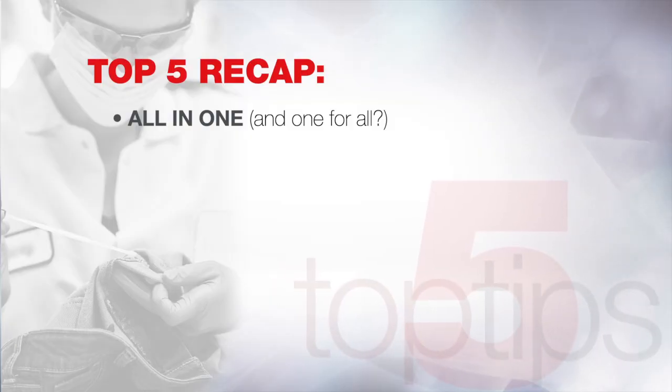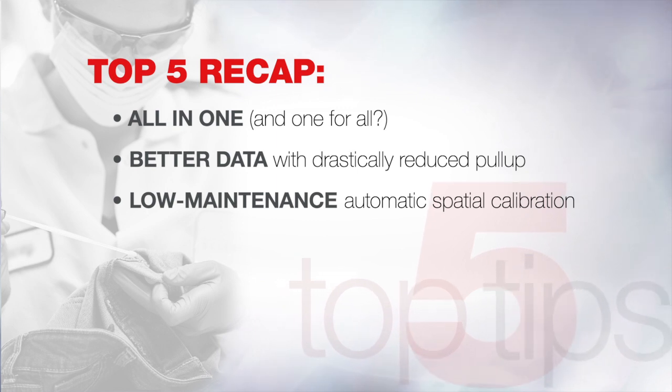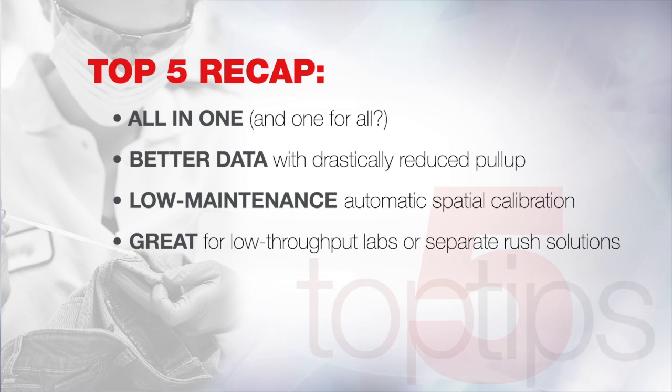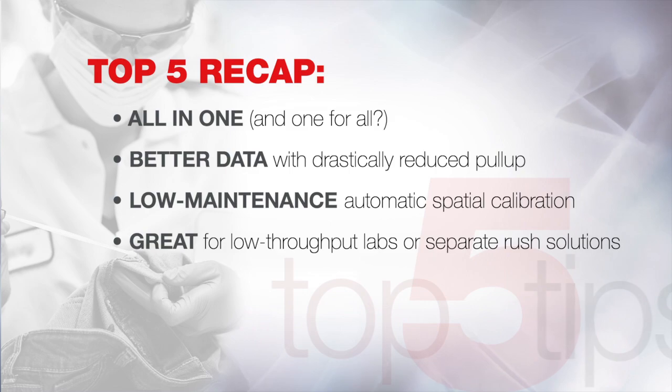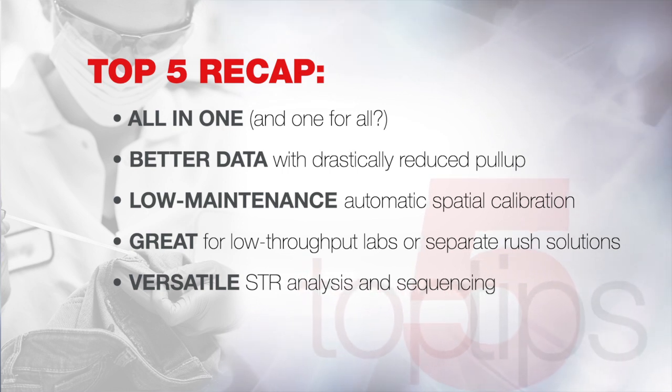Nice job, Nick. That was a lot of information. The SeqStudio Genetic Analyzer really does have a lot of new and exciting features. Let me recap my top five. Number one: all-in-one — the SeqStudio contains almost all components in one easy package. Number two: better data — new algorithms for drastically reduced pull-up and peak detection. Number three: less maintenance — the instrument performs spatial calibration automatically when the cartridge is inserted. Number four: implementation — great for low-throughput labs, universities, or larger labs that need a separate solution for rush cases without interfering with current batching methods. Number five: universal application support — you can perform both sequencing and STR fragment analysis without changing the cartridge.